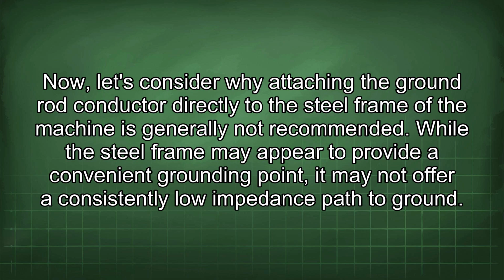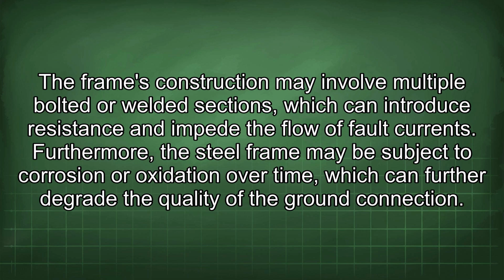Now, let's consider why attaching the ground rod conductor directly to the steel frame of the machine is generally not recommended. While the steel frame may appear to provide a convenient grounding point, it may not offer a consistently low impedance path to ground. The frame's construction may involve multiple bolted or welded sections, which can introduce resistance and impede the flow of fault currents.